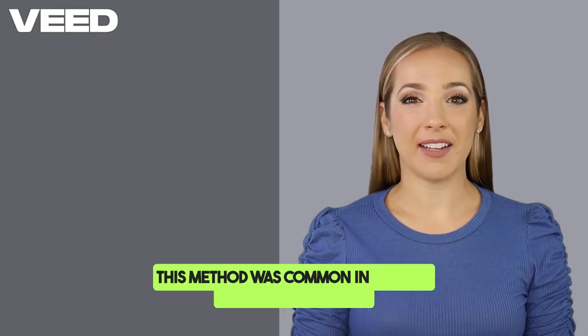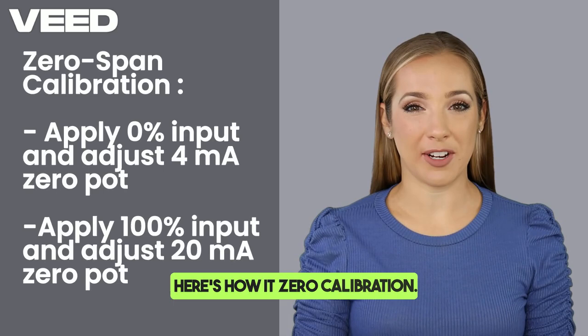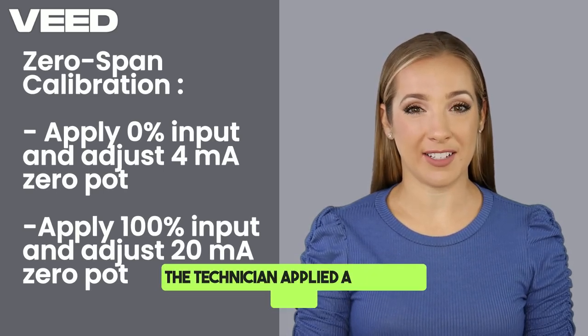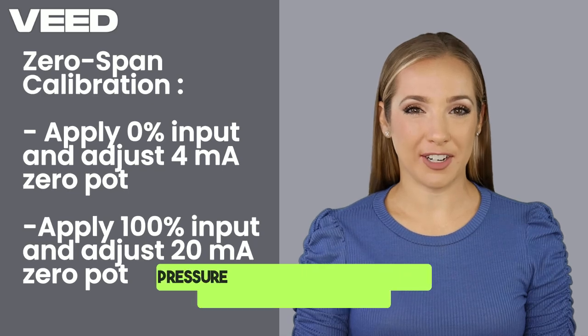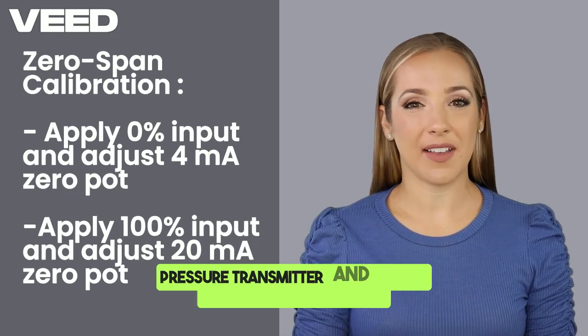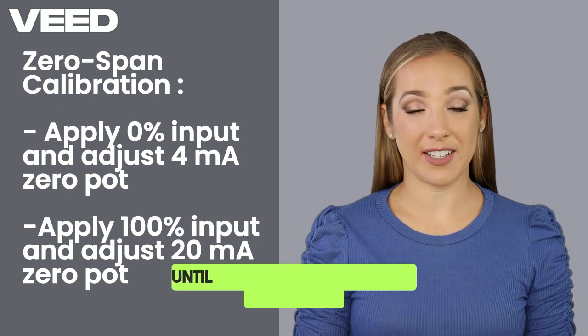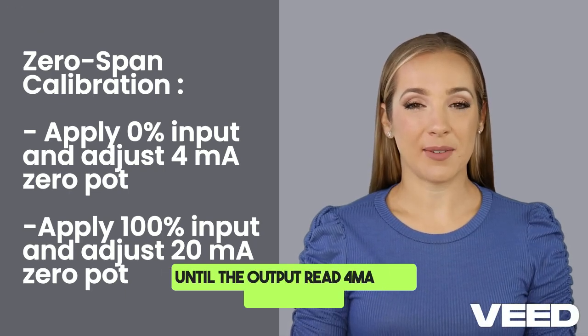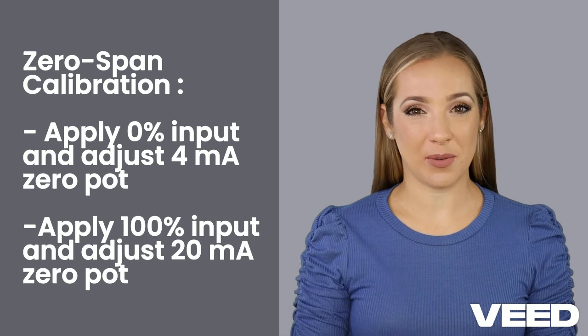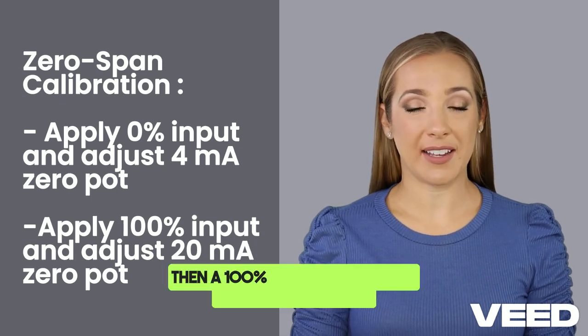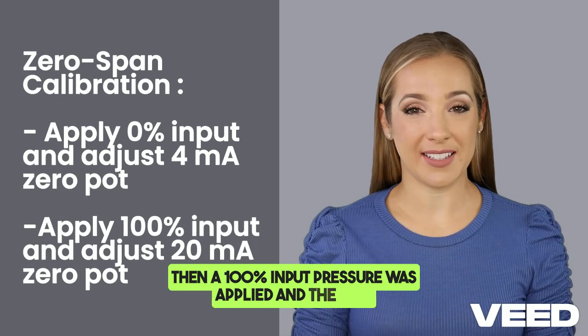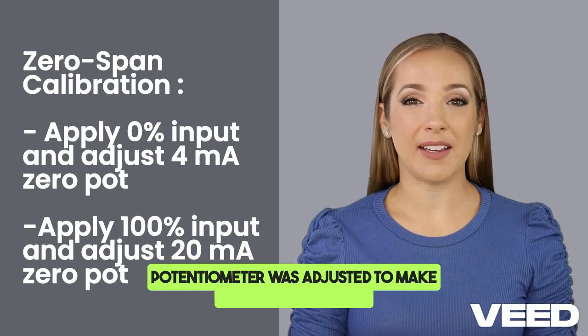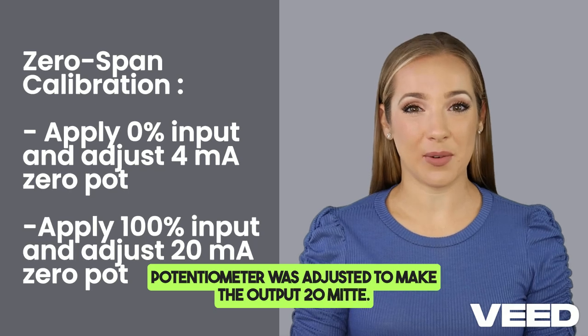This method was common in analog transmitters, which output a 4 to 20 mA signal. Here's how it worked. Zero calibration. The technician applied a 0% input, zero pressure if it's a pressure transmitter, and adjusted the zero potentiometer until the output read 4 mA. Span calibration. Then, a 100% input pressure was applied, and the span potentiometer was adjusted to make the output 20 mA.